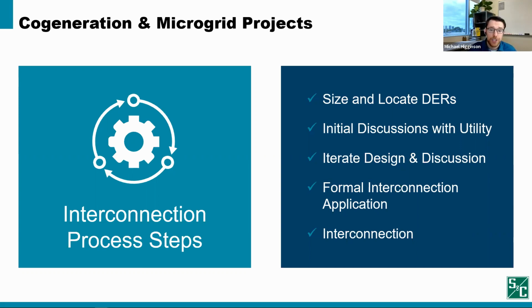A formal interconnection application must be applied for in the design phase, and this process can be lengthy, so starting early is usually best practice. Since we've already had initial discussions with the utility at this point, we can be more confident that the application will be approved and successful. Once the interconnection application is completed and approved, the interconnection itself can proceed. This can include upgrades to the local power system, for example some protection changes, voltage regulator changes, or service conductor size increases that we'll touch on momentarily.